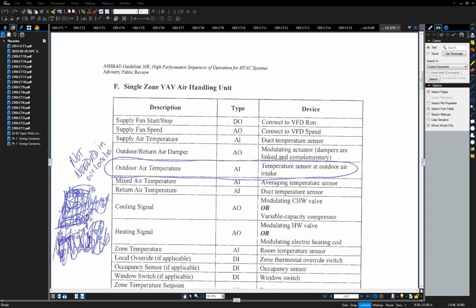Sure. So again, this standard is written, or the guideline is written with the idea of providing the best in class practice. But again, there's a wide range of practices, and certainly having one very high quality sensor available for outside air for economizer use and other controls, reset controls, is something that would be very good. So I think we agree with you. And if you do have one high quality sensor out there and you're using that for all of the air handling units, I would agree that that would probably be sufficient. Okay. Yeah, we just didn't know if it would start speccing it in new jobs just because it was standard, gets adopted and becomes common practice to do that everywhere.